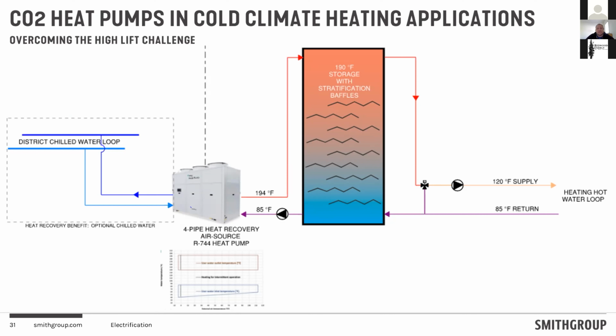So in this particular system, this is an air source heat pump with CO2 refrigerant. It also has a secondary heat exchanger that allows me to do free heat recovery off of a chilled water return line. So I can get simultaneous heating and cooling from this device. I can push that COP of 2.5, 3, up to 6, 6.5. That is how we cost-effectively electrify in cold climates.